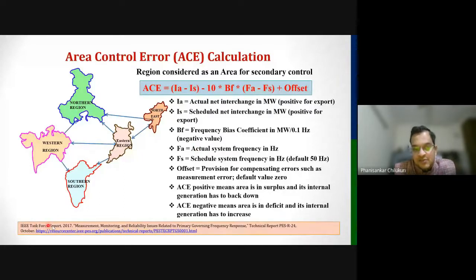There's an IEEE Task Force Report from 2017 which says that the optimal value for this bias factor is the frequency response characteristic. For example, if the southern region's frequency response characteristic is around 10,000 megawatt per hertz, that means 1000 megawatt per 0.1 hertz. So if you want to change frequency by 0.1 hertz in an isolated southern region, you have to change 1000 megawatt of generation.